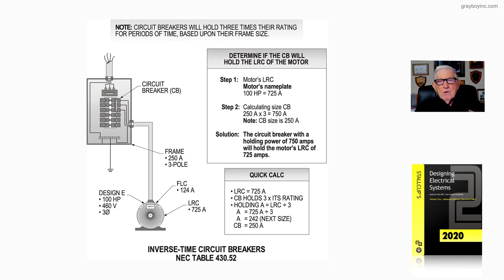If you didn't want to round it up, you could just start at 725, divide it by three, you come up with 242, round it up to 250, and that's going to allow your motor to start and run.